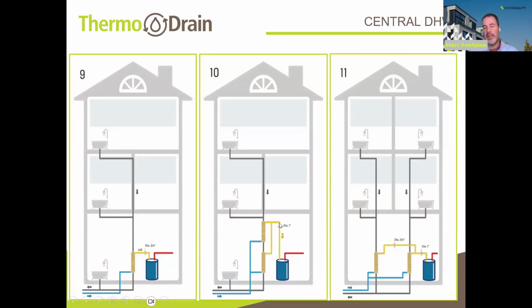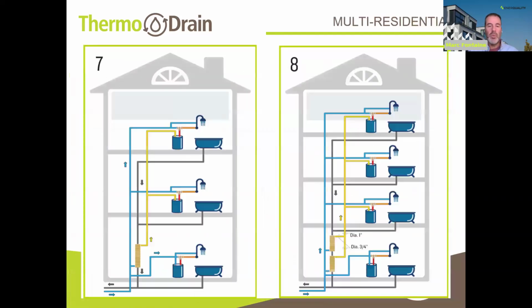If we have a higher building, let's say a 6 or 8-story building, then we can think of an arrangement where for every 2 dwellings we would put a drain water heat recovery unit. And if we had more dwellings above, we would put another drain water heat recovery unit servicing them, and we can go up and up and up that way for larger buildings.